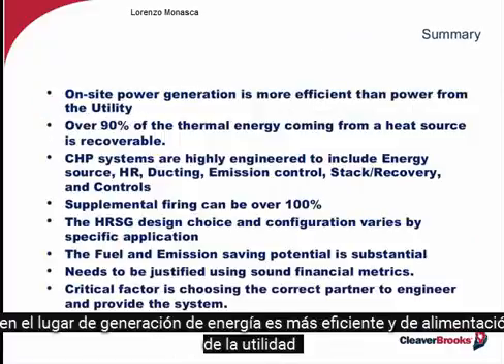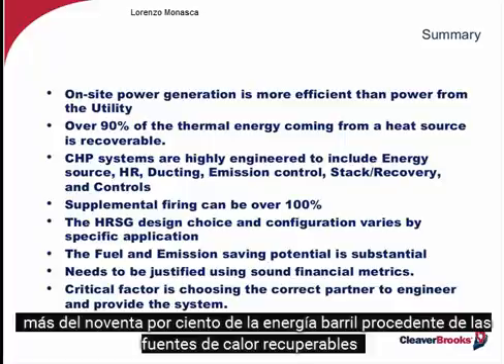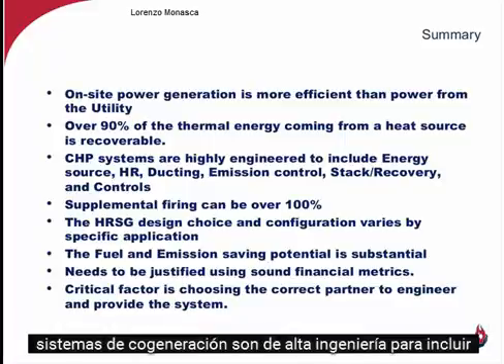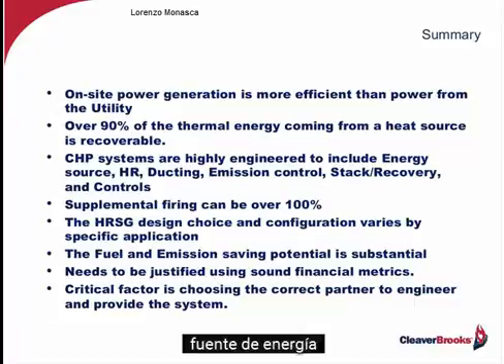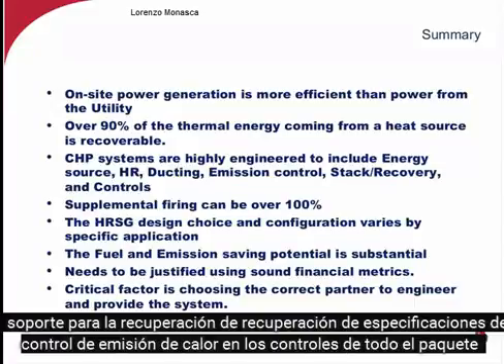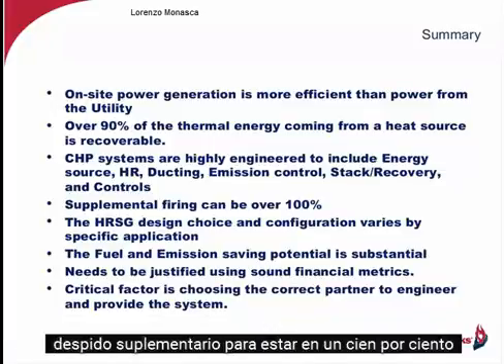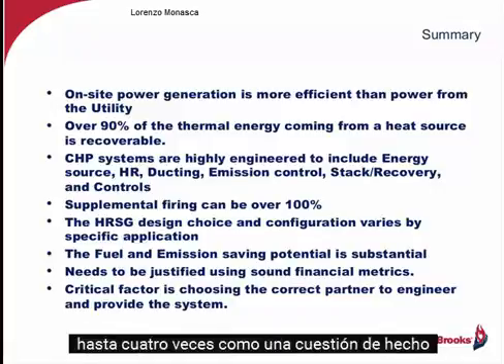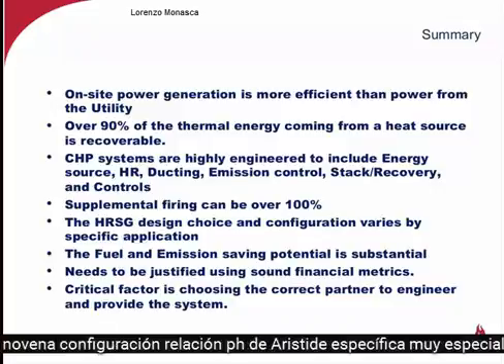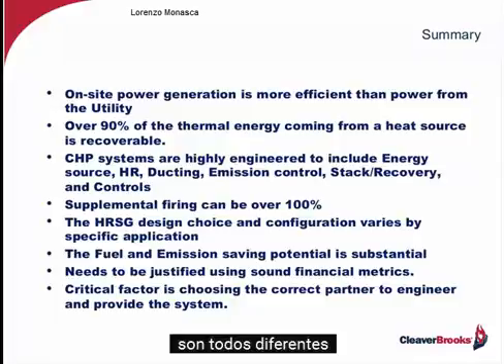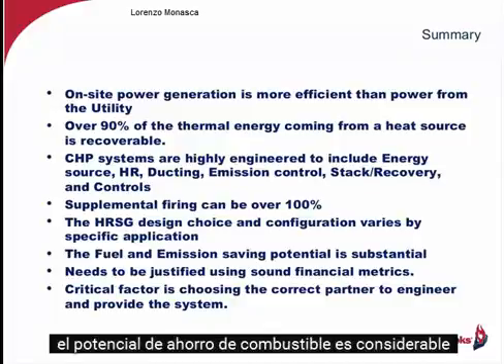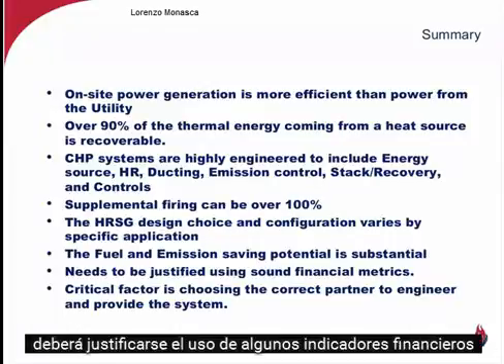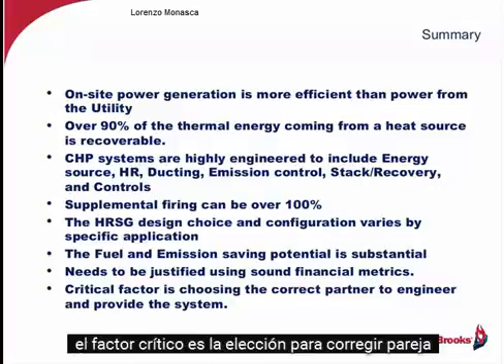So in summary, on-site power generation is more efficient than power from the utility. Over 90% of the thermal energy coming from a heat source is recoverable. Combined heat and power systems are highly engineered to include energy source, heat recovery, ducting, emission control, stack recovery, and controls, all packaged together. Supplemental firing can be over 100%, up to 4 times as a matter of fact. The HRSG design choice and configuration varies by specific application. They're all different. The fuel and emission saving potential is substantial and needs to be justified using sound financial metrics. And finally, the critical factor is choosing the correct partner to help engineer and provide the system.